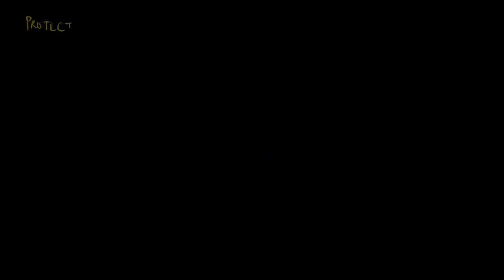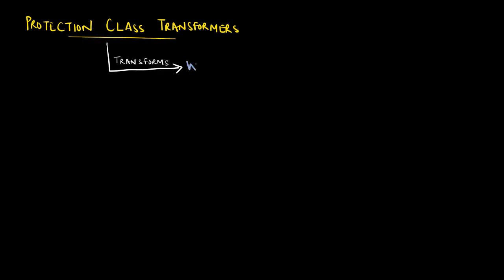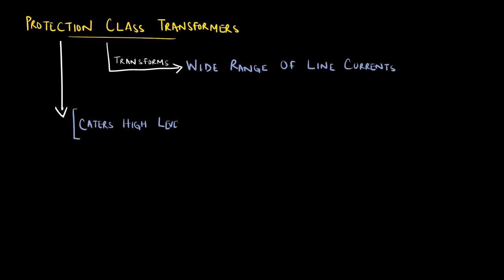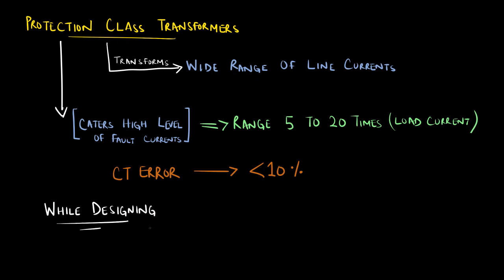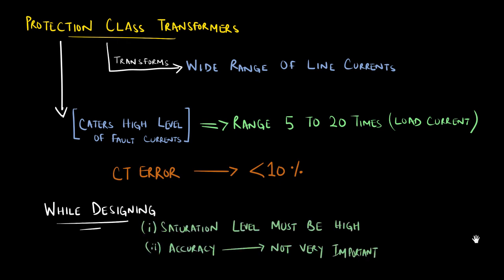Protection class current transformers are designed to transform wide range of line current with manageable amount of error. Typical range is 5 to 20 times the load current because short circuit currents can be very high values. We can expect up to 10% for the CT error. So protection class CTs should be carefully sized to make sure the CTs do not saturate.